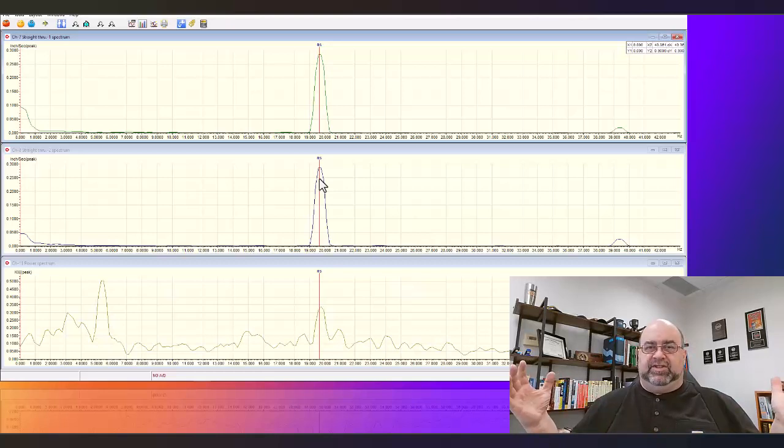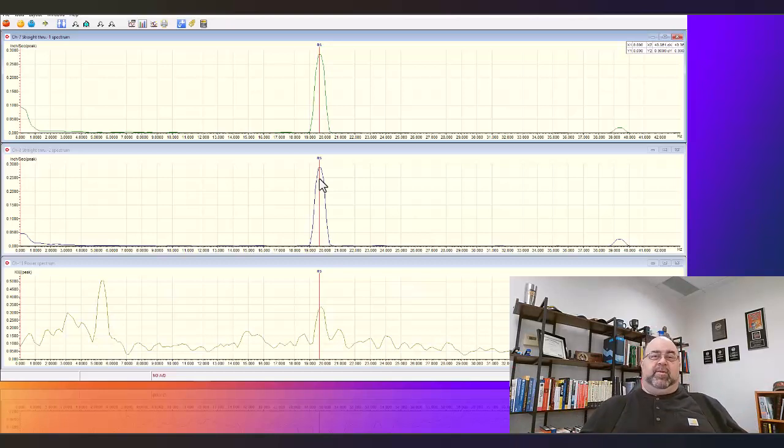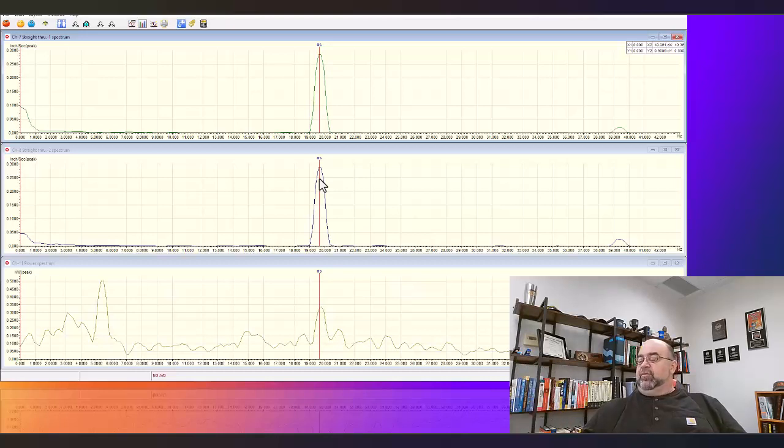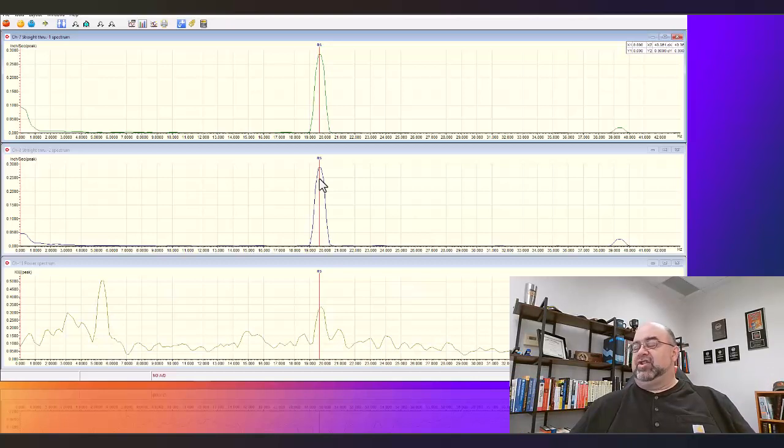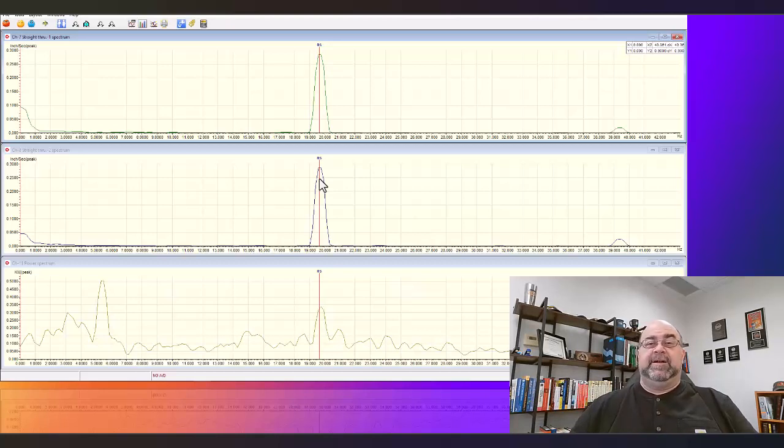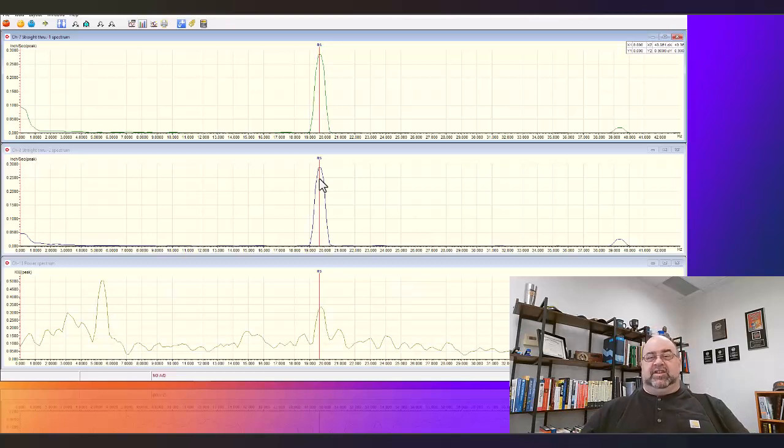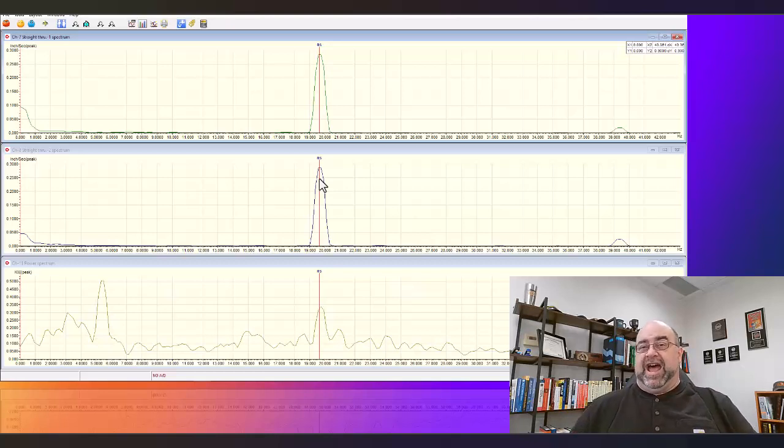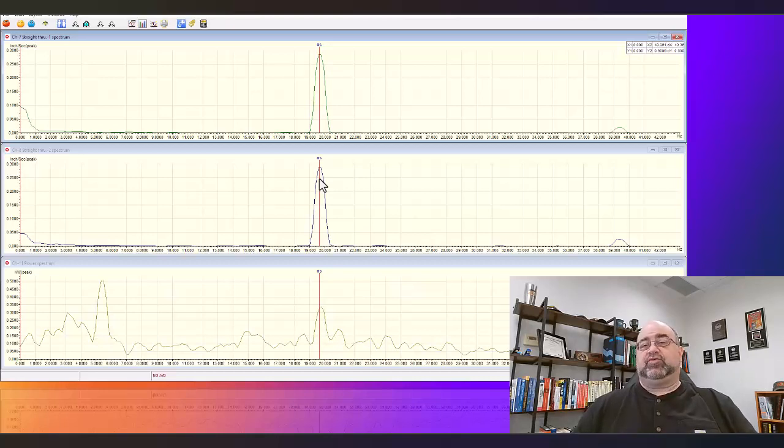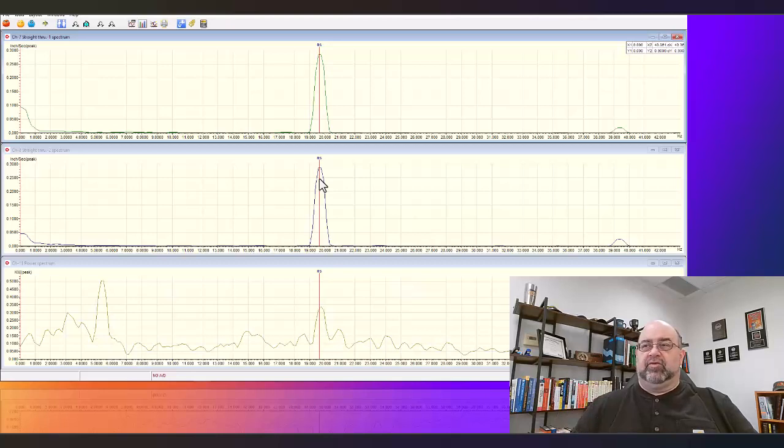So we'll see what happens. In any case just to give you an idea, I've seen some people come out with numbers at a conference. One of the continuous monitoring vibration guys said oh look we've got kilowatts. They had a bearing issue and then when they told me how many kilowatt hours it was for the year even at 8760 it was 125% of the entire machine's load. So that made no sense whatsoever. So beware when you see that stuff. In order to get a good solid accurate reading you need to have some type of kilowatt meter taking a look at all of your losses. And the nice thing is with ESA I can break that down into individual components. So that's one of the reasons why I stick to this as part of my energy studies.